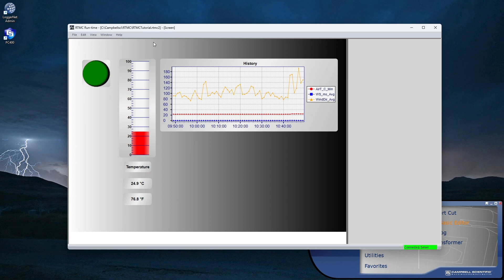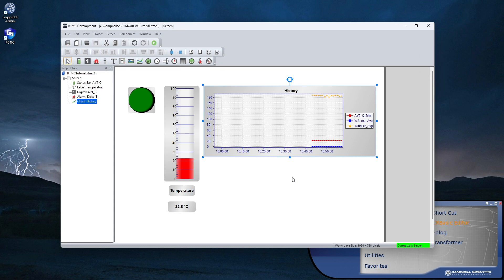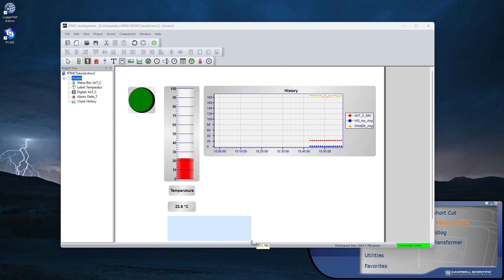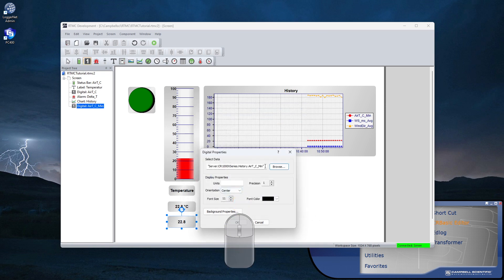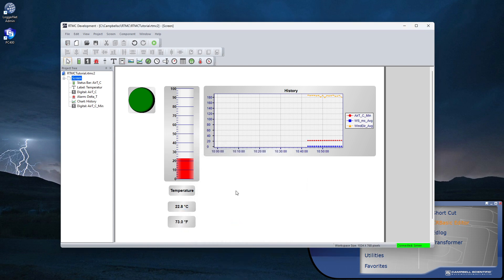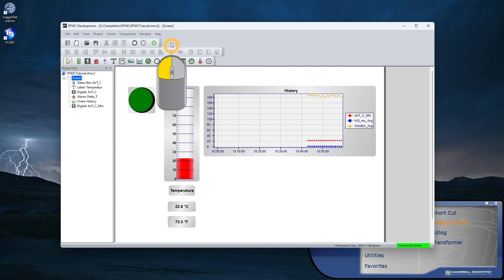Closing the runtime screen takes me back to development mode. Now I'll show how to use an expression. I want to display the air temperature in degrees Fahrenheit, so I'll add another digital display below the first. Put the cursor in the data selection field and enter the expression: multiply by 1.8 plus 32 to convert from Celsius to Fahrenheit. Use ALT+0176 for the degrees symbol. I now see both Celsius and Fahrenheit degrees being displayed. Expressions can include simple math, functions to manipulate strings, or more complex functions that deal with the state of a data value over time. The RTMC help has an extensive section on using expressions.